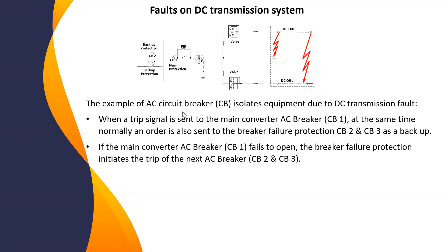When a trip signal is sent to the AC breaker, at the same time the breaker failure protection signal will be sent to circuit breaker 2 and 3. So in normal condition, in case of any fault, circuit breaker 1 will stop the power. But in case it fails, because we already sent the breaker failure protection signal to backup equipment, CB2 and CB3 will open, and by this the fault will be isolated.